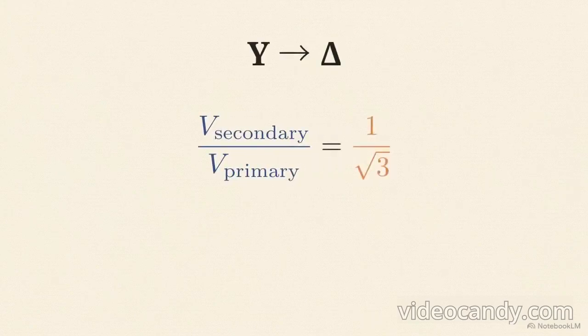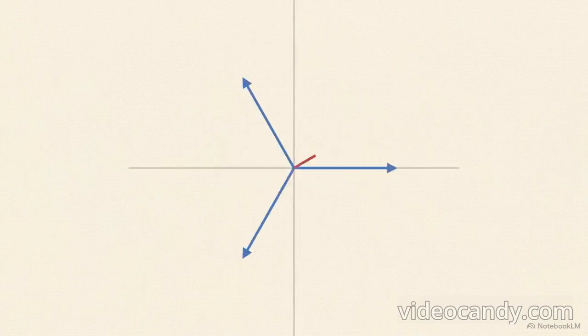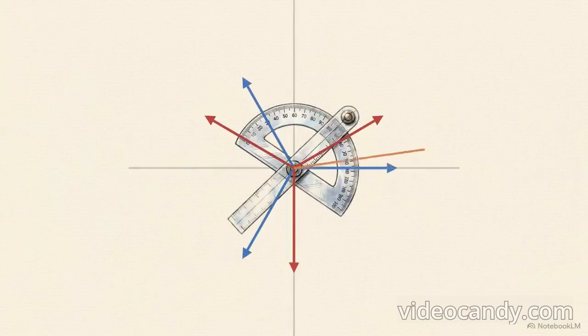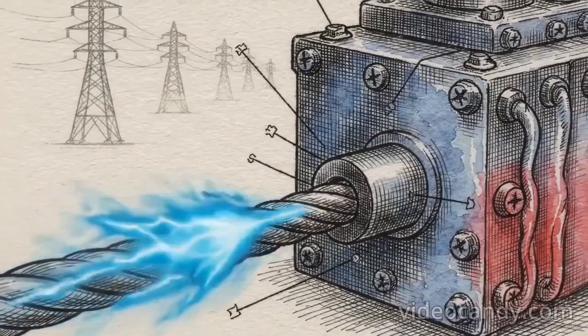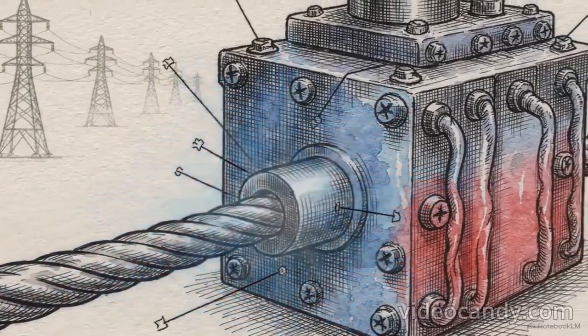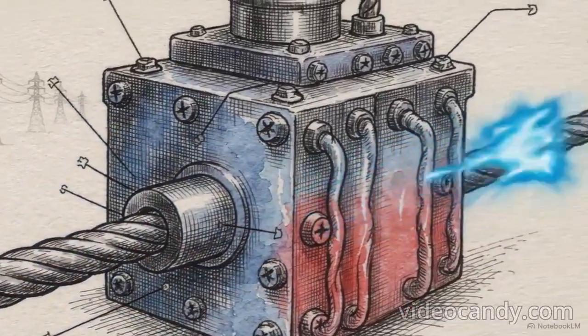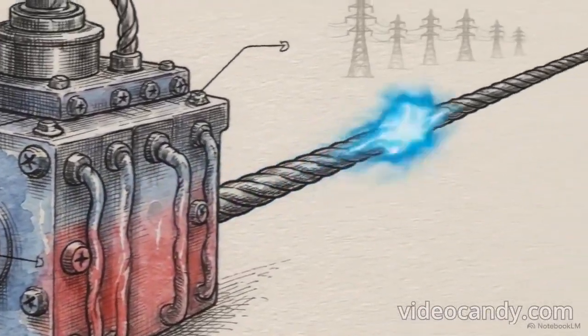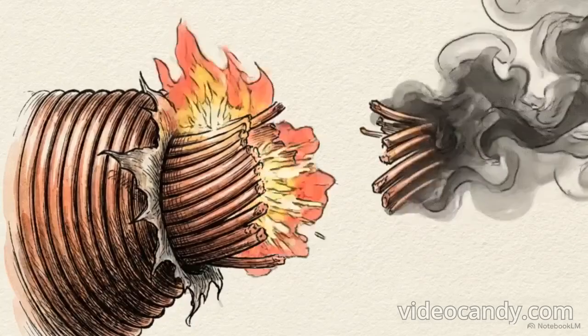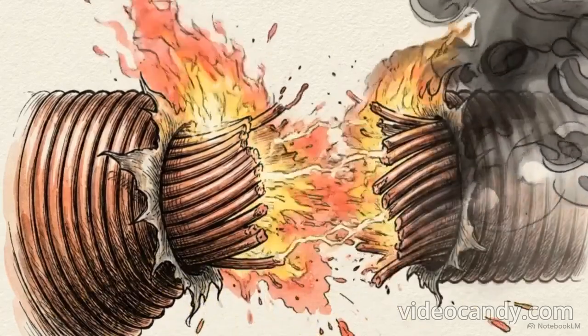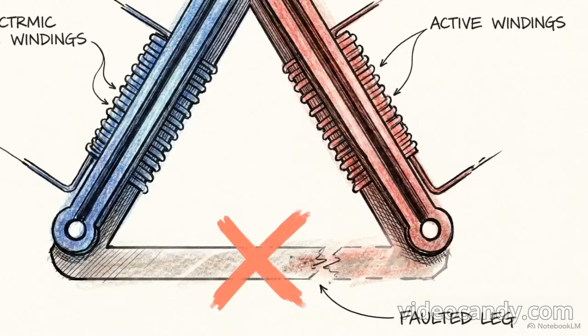Crossing these configurations alters the math. The ratio between the secondary and primary line voltages incorporates that same 1 over the square root of 3 factor, modifying the inherent transformation ratio of the coils. But crossing topologies introduces a strict geometric consequence. By linking a radial Y to a closed delta, you force an absolute 30-degree phase shift between the primary and secondary line voltages. Crossing configurations is the most efficient way to manage massive voltage jumps, but it permanently alters the temporal phase alignment of that entire grid segment.